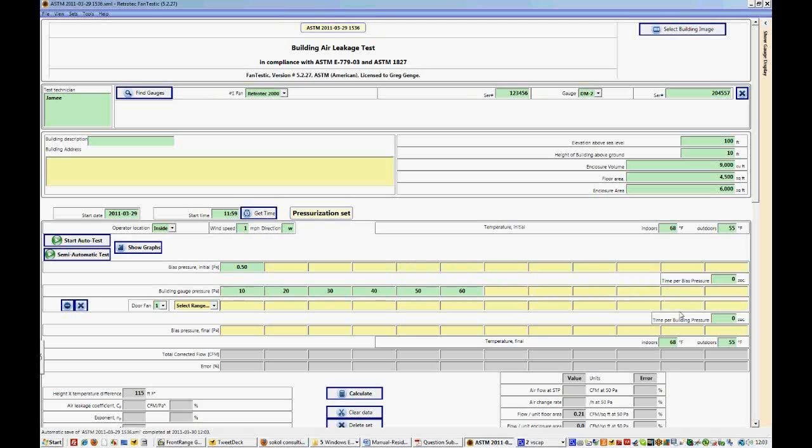And we'll put in here the time per building pressure. So if you've set your gauge up to read at a 20 second time average, then we have taken building pressures for 20 seconds. And we did the same thing for the bias pressures. And it is required for ASTM that the time per building pressure and per bias pressure be taken for greater than 10 seconds each. So we have succeeded in passing that deviation statement.